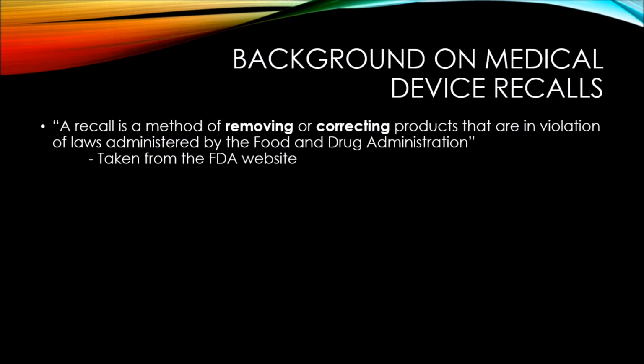Great, so now moving on, I want to talk to you guys about medical device recalls, and the first thing to do is to define what it is. So according to the FDA, a recall is a method of removing or correcting products that are in violation of laws administered by the Food and Drug Administration. So I wanted to emphasize removing and correcting because in my head, before this project, a recall was just removing a device from the market, but that's not necessarily what it means.